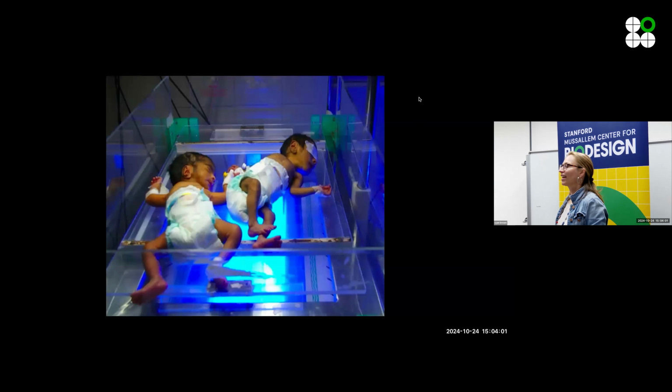It's not everywhere. So the poor baby on the left, the baby's not actually getting much phototherapy, right? Because there's 6 bulbs and 3 of them are burned out. And then also there are these giant diapers, which is another issue, right? Because you often see that in hospitals too, that there are only diapers available for the babies who are that small, which is limiting the skin exposure. If you need to get the blue light through the skin, that's going to be an issue. So this is very common. This photo is from a large public pediatric hospital in southern India.